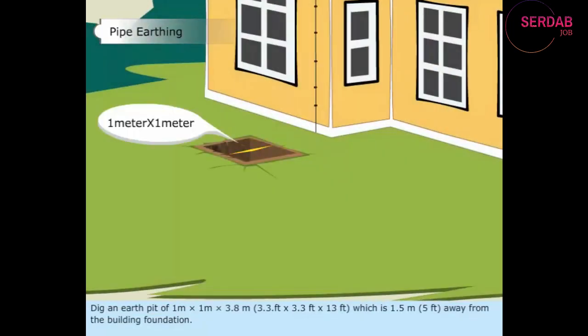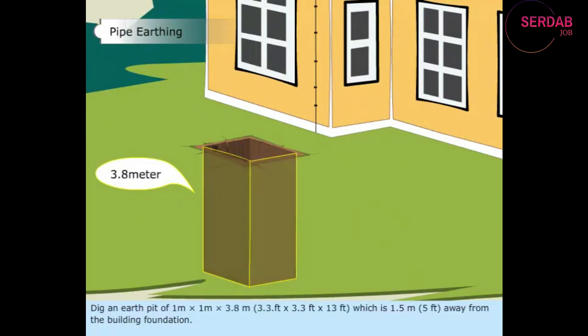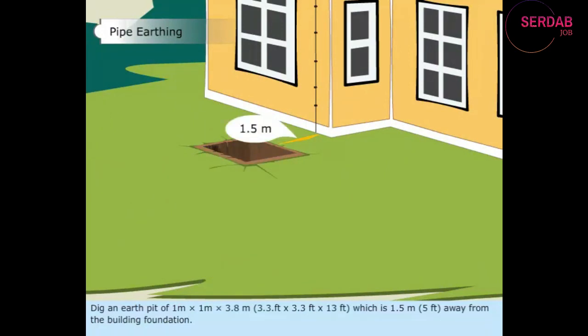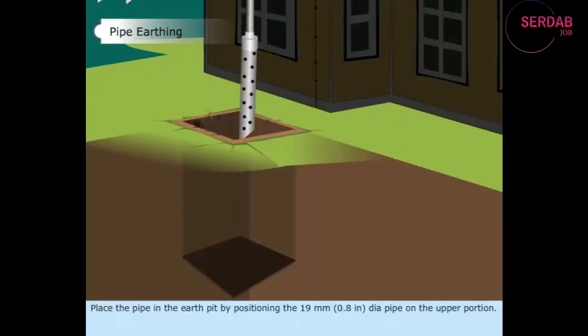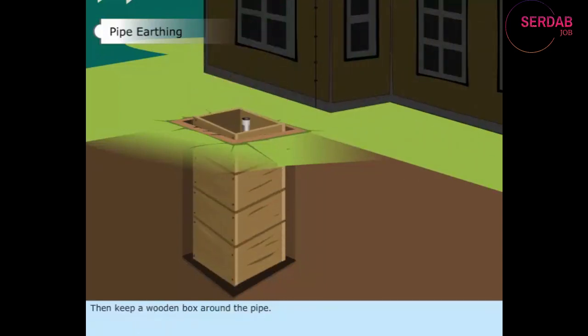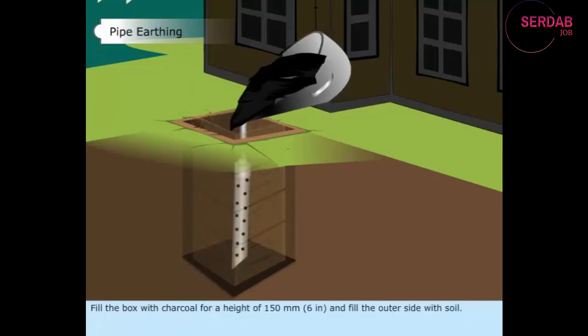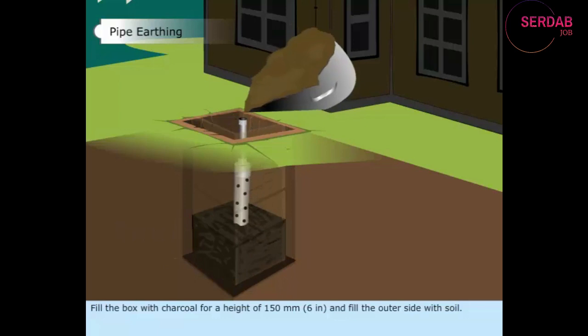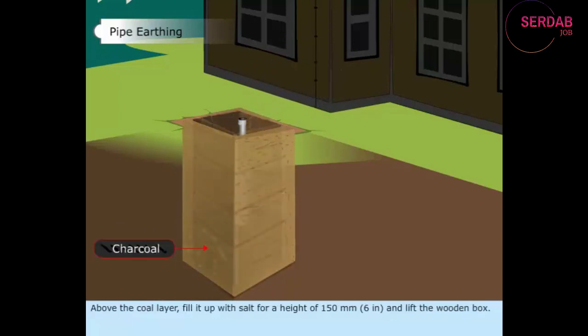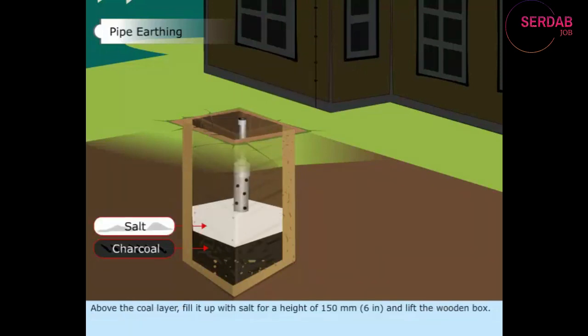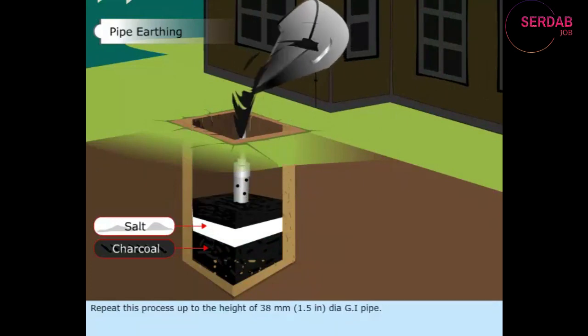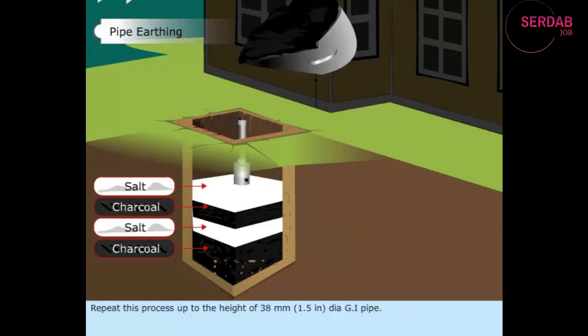Dig an earth pit of 1 meter by 1 meter by 3.8 meters, or 3.3 feet by 3.3 feet by 13 feet, which is 1.5 meters, 5 feet away from the building foundation. Place the pipe in the earth pit by positioning the 19 mm, 0.8 inch diameter pipe on the upper portion. Then keep a wooden box around the pipe. Fill the box with charcoal for a height of 150 mm, 6 inches, and fill the outer side with soil. Above the coal layer, fill it up with salt for a height of 150 mm, 6 inches, and lift the wooden box. Repeat this process up to the height of 38 mm, 1.5 inches diameter GI pipe.